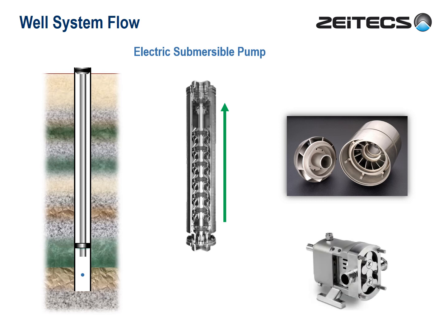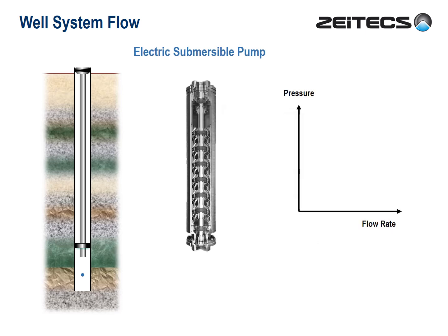This should not be confused with a positive displacement pump. Fluids can move through an ESP independently of the pump speed, and the amount of kinetic energy added to the fluid is a function of the relative speed of the pump and the fluid. If fluids move through the pump at a substantially slower speed than the impellers are spinning, the fluid will be accelerated and pressure will be generated. But as the flow rate increases, this effect naturally becomes less. Conversely, when fluids move substantially faster than the impellers, the pump actually hinders the flow and acts as a choke.